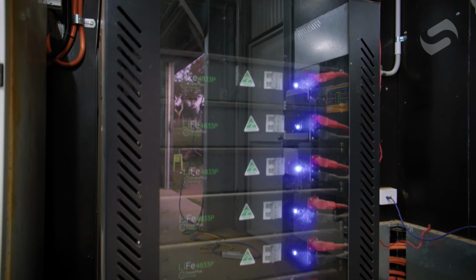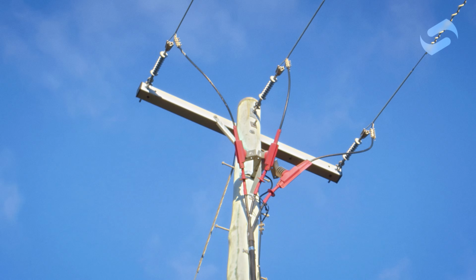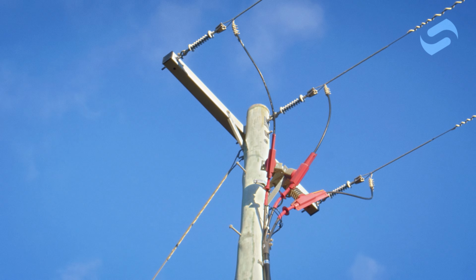The choice was between going fully off-grid, which mandated a petrol or diesel generator as backup, or getting a grid connection. We knew grid connection would only really be for backup and for export, and price-wise they were pretty comparable. However, electricity from the grid is cleaner than running a generator, and I don't have to maintain the grid like I'd have to maintain a diesel generator. Having the grid available for export when we've got excess power, financially you're better off. So it was an easy decision because the cost of the generator and the cost of getting the grid connection were very similar. If we'd had to put a new transformer on the pole, it would have been 40-50 grand for sure, and I would have just poured that money into a bigger battery, bigger solar array, everything.